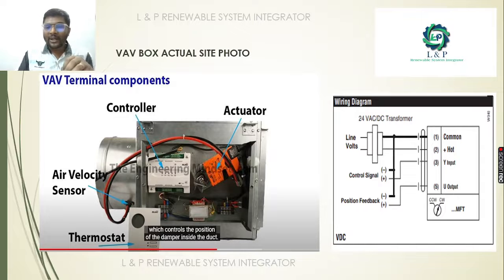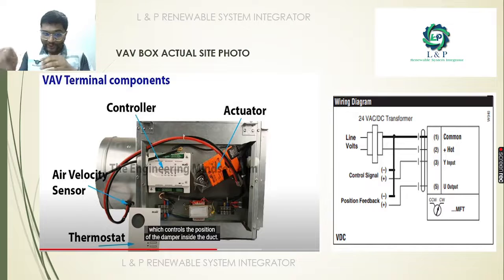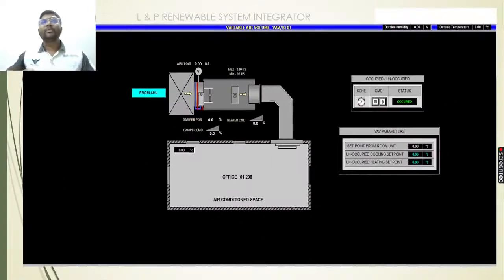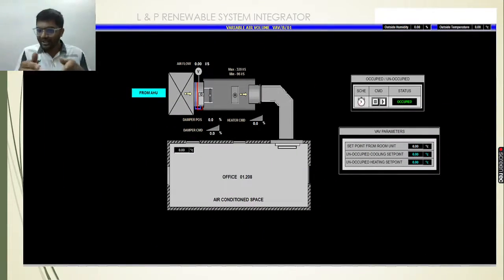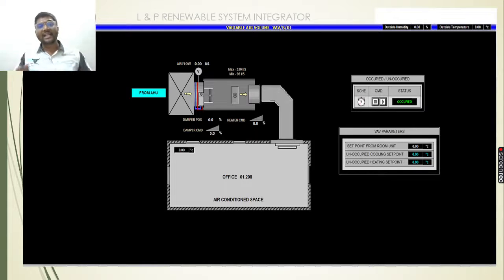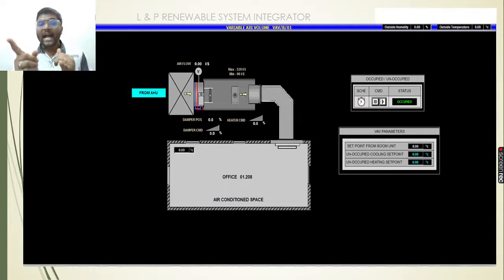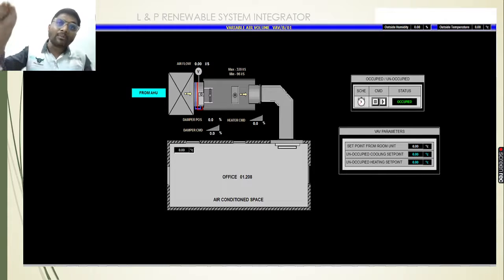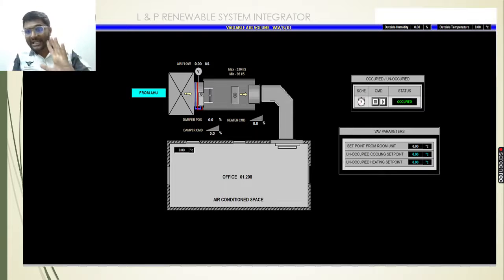For actuator wiring, it needs a power supply to work, a control signal to send, and a feedback signal to receive. Mostly for actuators we use 0–10V DC. For graphics, this is the typical display you can use — enhancements can be made based on your needs. Basically, the graphics should show whether the system is occupied or unoccupied, the set point temperature for occupied and unoccupied modes, the damper command given, the feedback received, and if a duct temperature sensor is installed, the supply duct temperature as well.